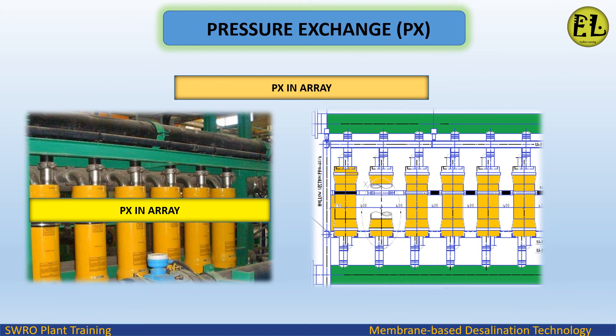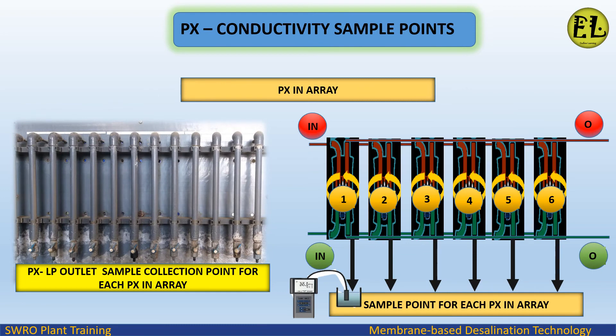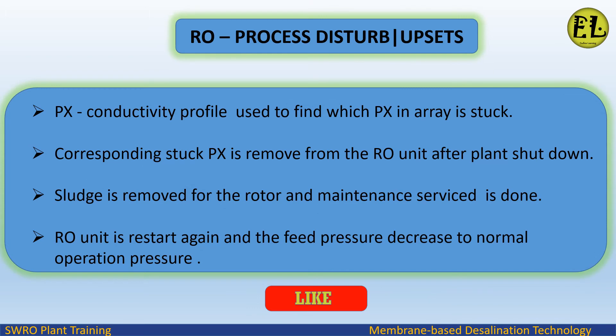A pressure exchanger PX conductivity profile is performed to verify which PX units have stopped rotating in the PX arrays. Water samples are collected at each PXLP outlet line in the PX array. The PXLP outlet with conductivity close to seawater intake conductivity is identified — the PX conductivity profile is used to find which PX in the array is stuck.